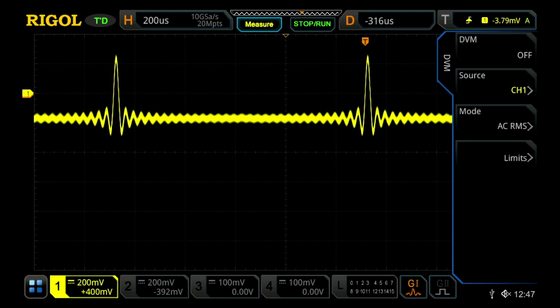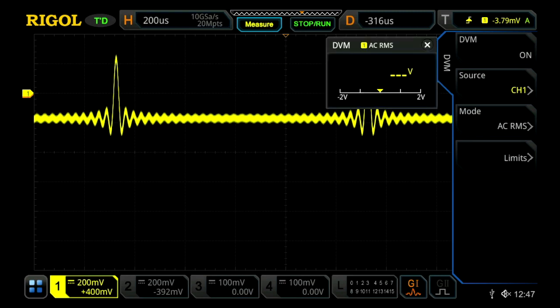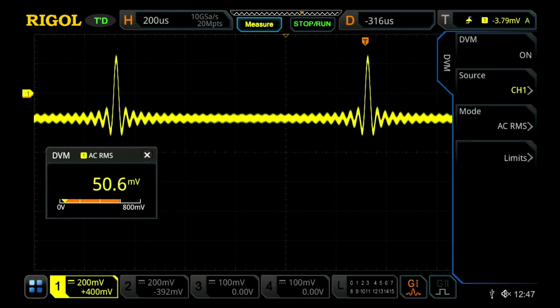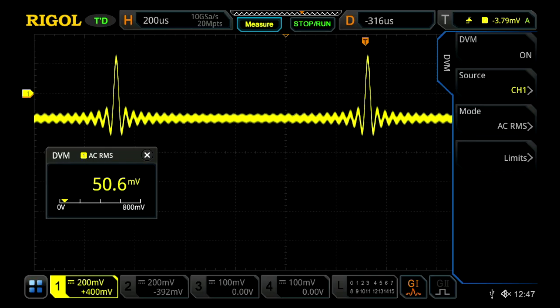This will bring you to your digital voltmeter measurement menu. This allows you to select your source, your mode, and your limits. Let's turn it on. We can drag this on our screen, and it's now showing roughly 50 millivolts for our channel one signal.